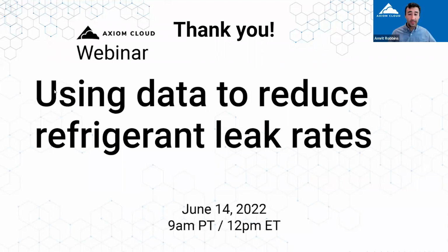That's again by looking at these trends. If things are going along in steady state for days or months or years, and then suddenly there's a change in that trajectory, the date on which that change occurred is typically the start of that problem. If you're going along like this and then suddenly you see a dip, when that dip occurs, that's when the problem starts. That's how we're able to say this problem started 3 to 7 days ago, and that's our target basically, and we are consistently achieving that target across the fleet today.